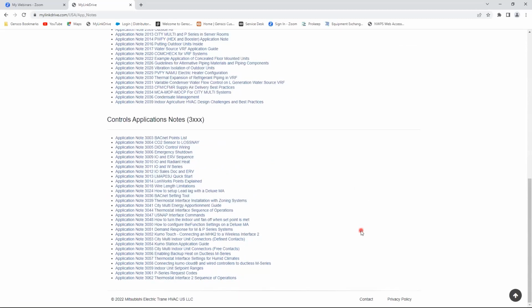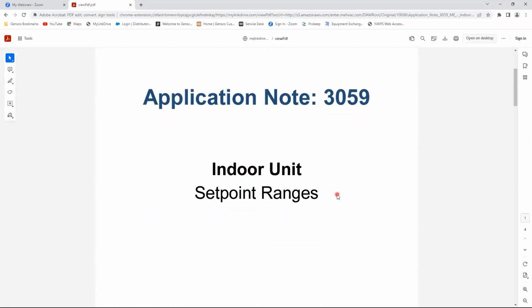Now, one of the things we get tons of calls on here is people plug in an MHK2 to an air handler, say. Well, they're wondering why they cannot get their cooling set point below 67 degrees. Well, right here on app note 3059, if you click on this, it covers set point ranges. So when you plug in an MHK2 into an air handler, I will tell you that it does not automatically sense the temperature from the MHK2. You have to go to mode 2 and change that to 3.